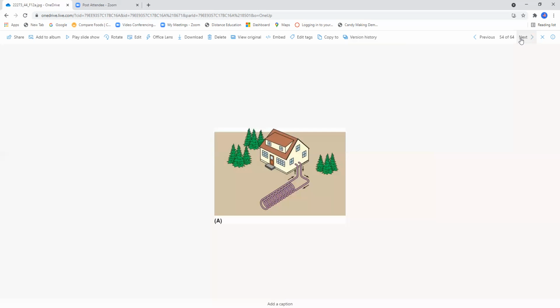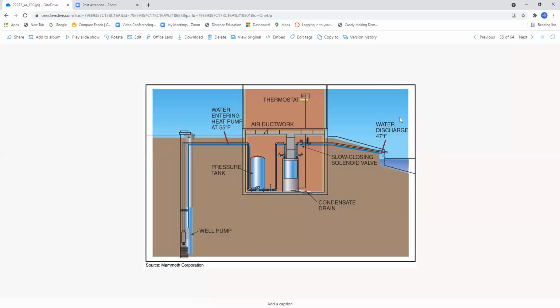This would be figure 44.12, and this will be a Slinky groundwater loop. Remember the Slinkies? Okay, here we have a situation where you're using a well, the water entering the heat pump at 55 degrees. You got the pressure tank, and then of course you got the machinery here. You got the duct air handler, ductwork for the house, the thermostat up here, a slow closing solenoid valve, and a condensate drain. So you'll have an evaporator coil inside that blower cabinet.